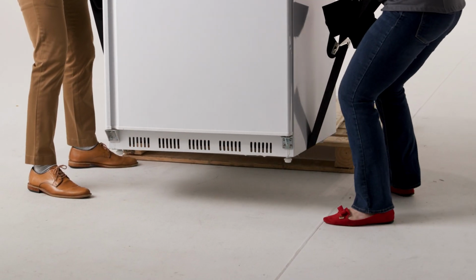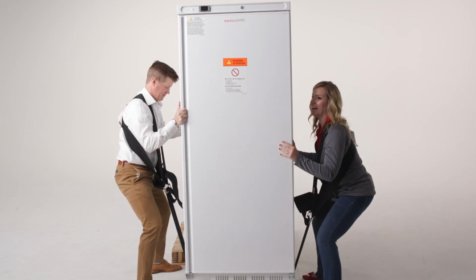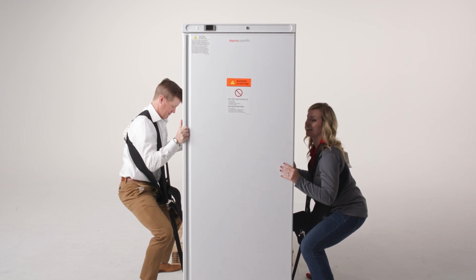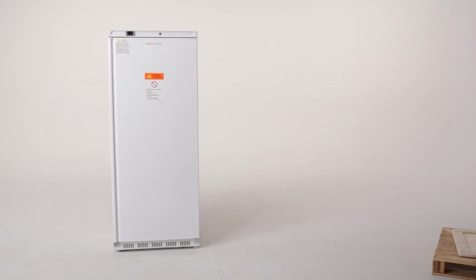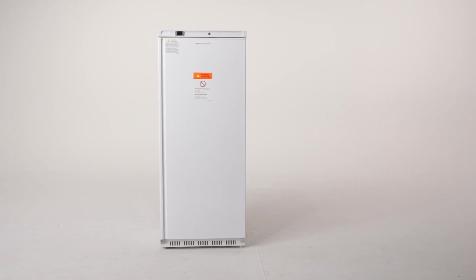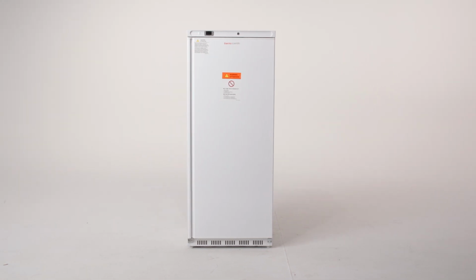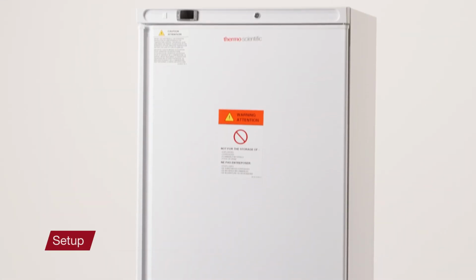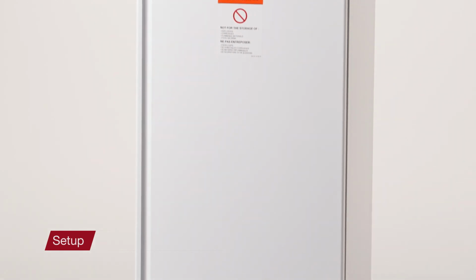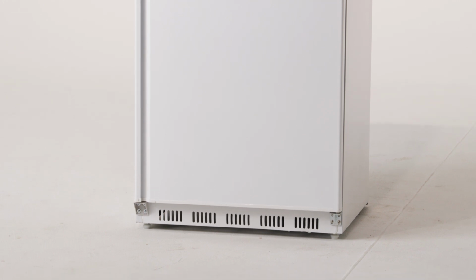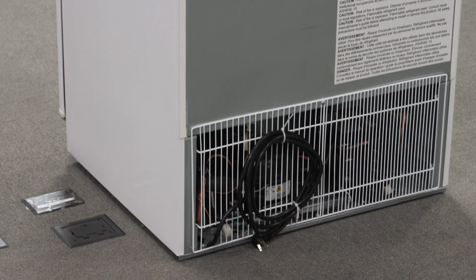Follow recommended safety processes and use appropriate equipment when lifting and moving the unit. Once removed from the wooden pallet, the unit can be rolled into its location and the pallet can be properly disposed of. Let the freezer stand upright for approximately 24 hours before connecting it to the power. This reduces the possibility of malfunction in the cooling system from improper handling during transportation.